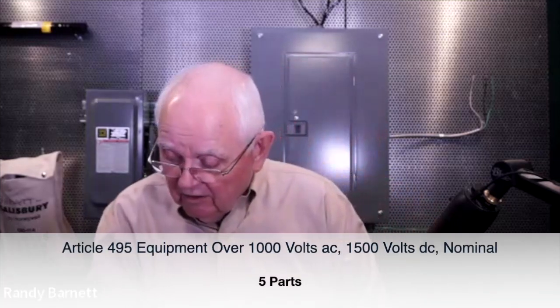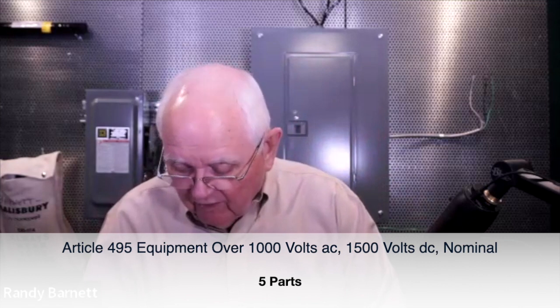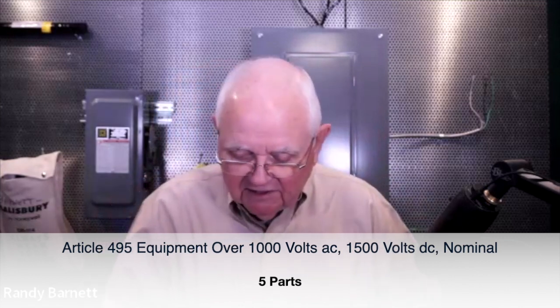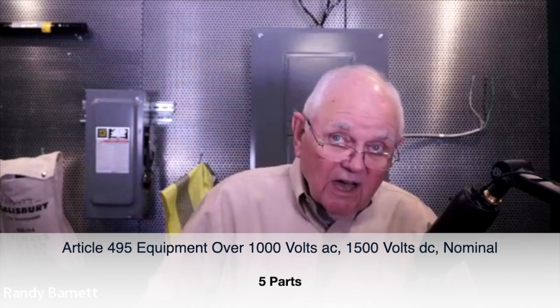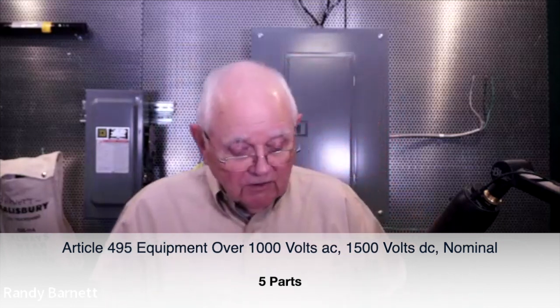Let's take a quick look now at Article 495 on high voltage equipment and see how that is divided up. Article 495 has 5 parts. The first is some general information, the scope and so forth, and it tells us that other articles would apply. The equipment specific provisions for installing that equipment, as far as maybe spacing requirements and back feeds, and if we have a back feed, we have to have signage there and so forth, are all covered in part 2.